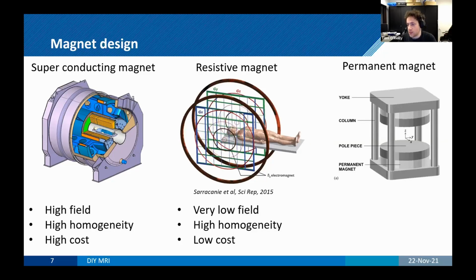Then you have the resistive systems. This is a nice one from Matt Rosen's group, running at 6.5 milliTesla - that's 3 orders of magnitude lower than the superconducting systems, just because you can't push too much current through the wires due to I squared R heating. Typically these are very low field, but they have the same benefit as superconducting systems in that you can wind that wire in any way that you want, so as long as your manufacturing tolerances are decent, it's quite easy to get high homogeneity.